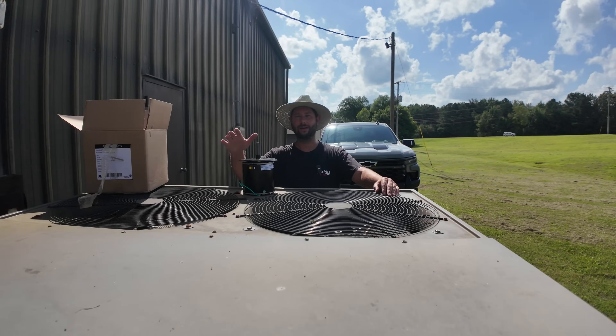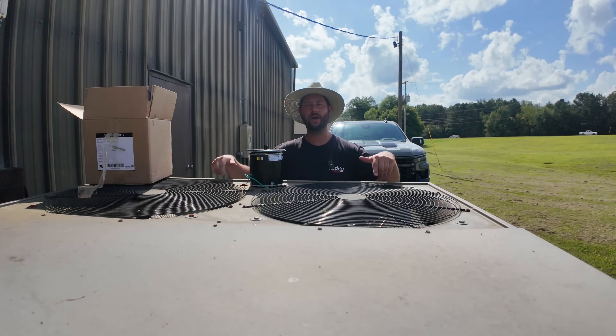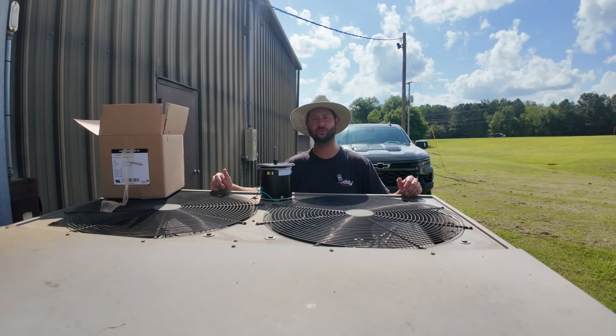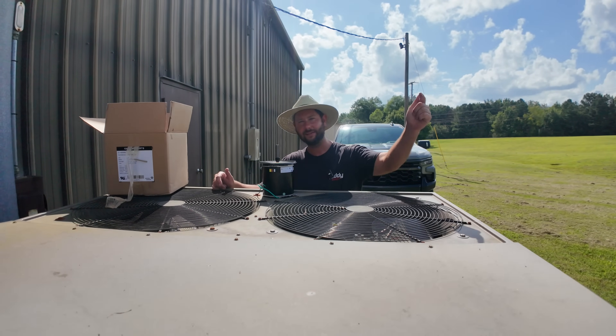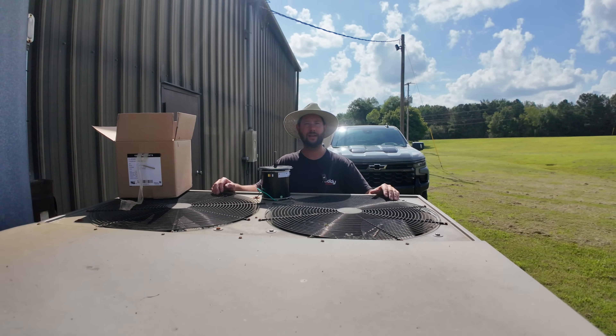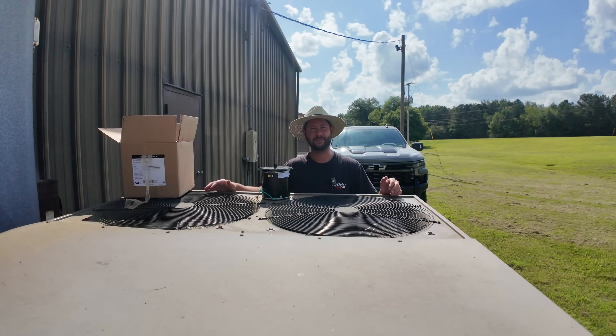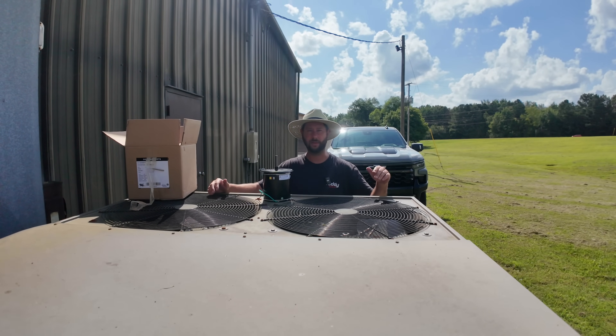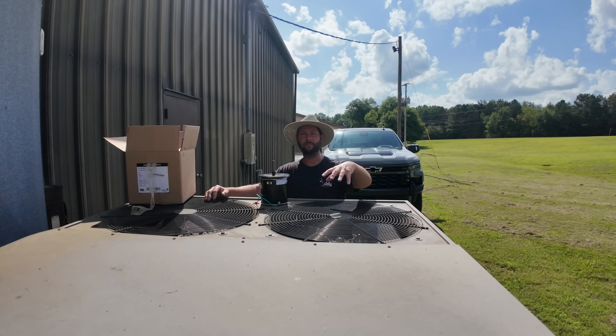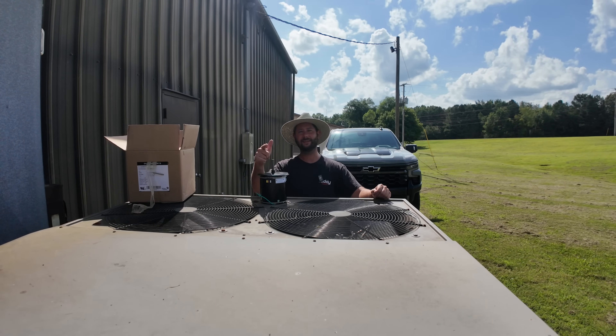How do you replace a condenser motor on a commercial package unit? Today we're going to be replacing one of these outdoor motors on this commercial package unit. I got a call — a customer said they heard a squeaking noise, and I had to come out and replace the indoor fan belt. After I replaced the fan belt and turned the unit on, I heard a terrible noise, which was an indication that we had a motor that was going to go out. I asked the customer, do you want to go ahead and order the motor and have me come out and replace it, or wait till it goes out? They said, let's go ahead and get it done. You're watching HVAC Tips for Technicians. This is Taddy Digest. I'm Tad. Let's get started.